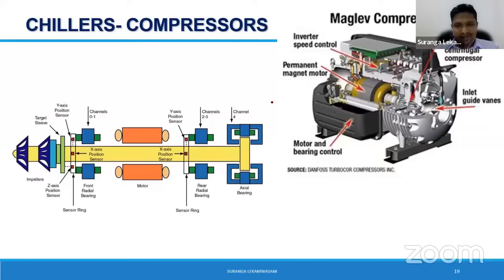Then the most controversial member of the chillers, right? The magnetic bearing chiller. That is called a maglev compressor, a magnetically levitated compressor. It is nothing complicated actually. Previously, all the chillers had bearings known as hydrodynamic bearings or journal bearings. This is the journal, this is the rotor. In between, you have a fluid layer. Due to the rotation, the fluid layer exerts a vertical lift force, a sort of hydrodynamic lift. But that oil is a headache, because you have to manage it. The oil gets diluted with refrigerant, deposits in the heat exchangers and reduces your heat transfer efficiency.